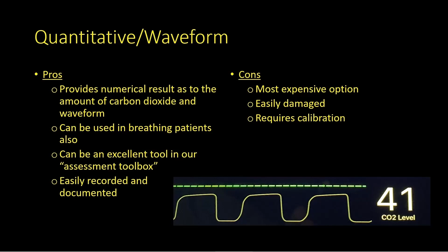Now, typically these may be installed as a feature or a module in your standard cardiac monitor, in which case they usually work based on one of two principles. The two common configurations we see are mainstream or side stream. Now, the picture here shows what we call a mainstream adapter. The adapter up in the top center of the picture is attached between the tube and the bag valve mask. That probe snaps onto the side of it there and actually reads across the adapter to determine the amount of carbon dioxide. Now, this is monitoring right at the end tidal section at the end of the ET tube and works very well. They don't require as much calibration as some other units, and again, works very well, gives us not only the waveform, but the numerical, and the other end is plugged into the monitor where it will feed it and record it along with the rest of our EKG information and anything else we have.